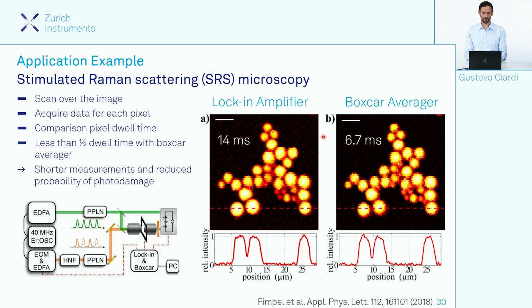And what they found is that in this case, Boxcar averaging led to a pixel dwell time, so for each pixel of this picture, that was half that of lock-in amplification. And this is good, because it not only reduces our measurement time by half, which is always something we aim for, but also avoids the photodamage that can occur when investigating delicate biological samples.